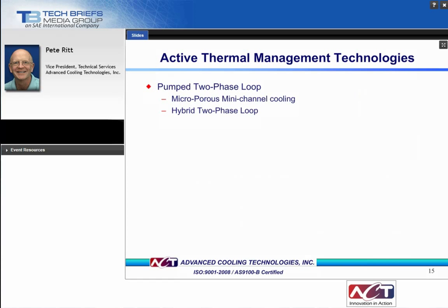Thank you. Next, we'll move to active pumped two-phase systems. When we talk about active two-phase solutions, we are typically referring to those systems which require input power to operate. Here, we will explain the pumped two-phase system, highlighting some of its inherent advantages as well as some challenges. Then we'll look at two recent advancements, microporous mini channels and hybrid two-phase loop, which address some of the issues that have been found with pumped two-phase systems.